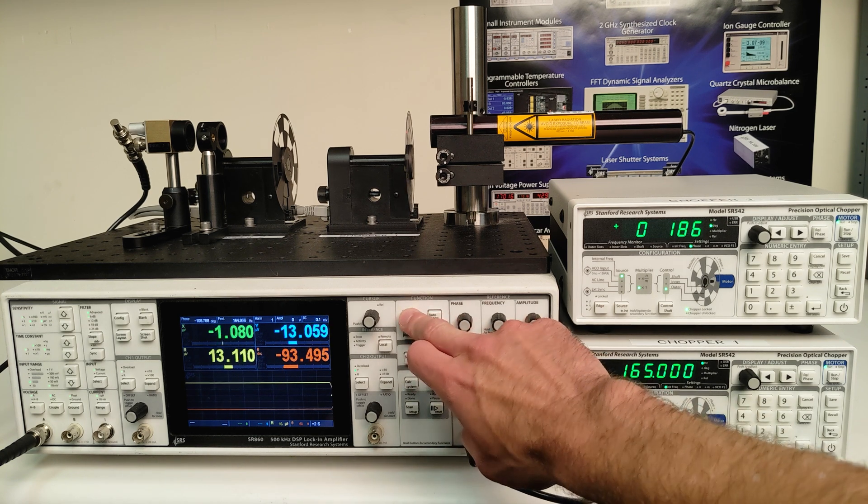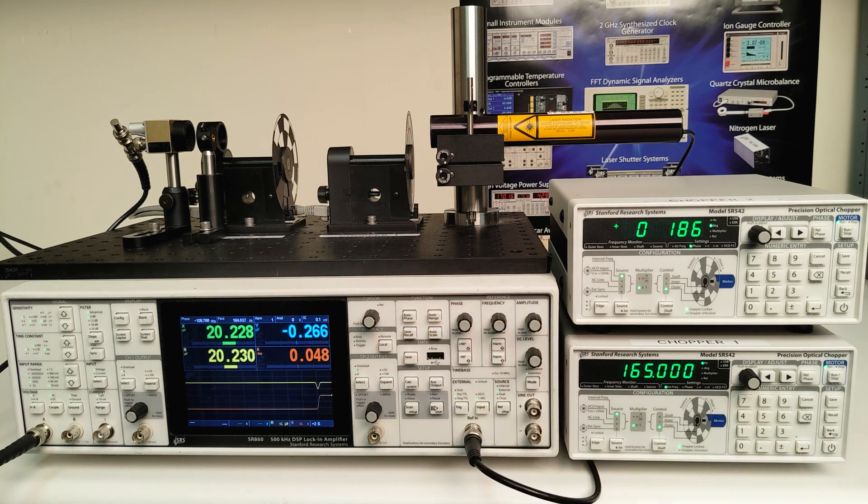These are the baseline R and theta values for the singly chopped beam. Let's go ahead and press auto phase to consider this zero phase, and any departures will now be easier to see.